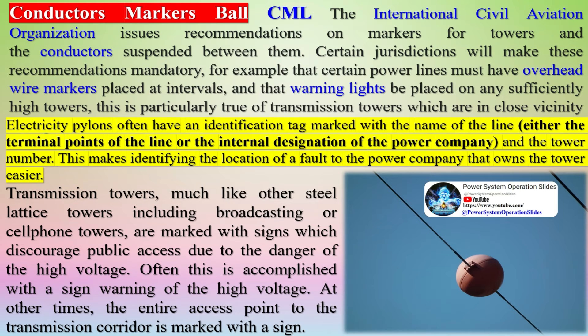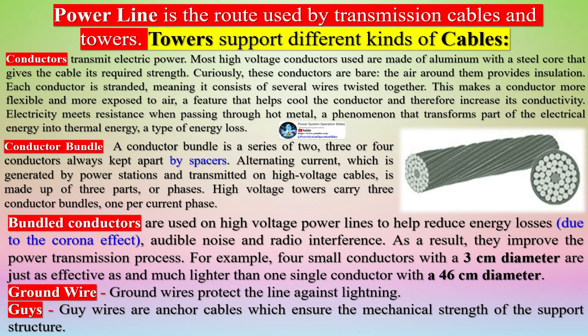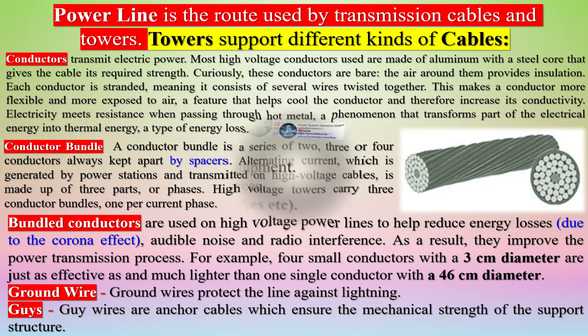The International Civil Aviation Organization issues recommendations on markers for towers and the conductors suspended between them. Certain jurisdictions make these recommendations mandatory — for example, requiring overhead wire markers placed at intervals, and warning lights on sufficiently high towers, particularly those in close vicinity to airports. Transmission towers, like other steel lattice towers, are also marked with signs discouraging public access due to the danger of high voltage, either on the tower itself or at the entrance to the transmission corridor.